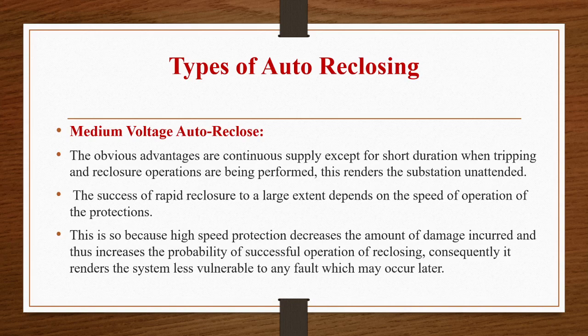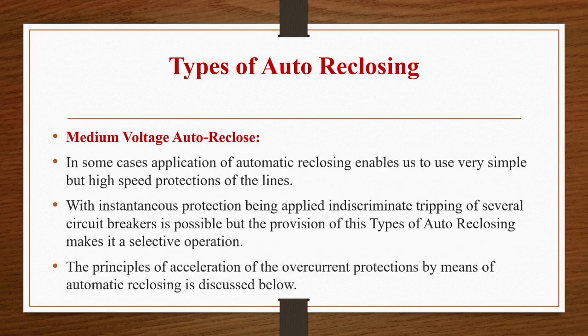This is so because high speed protection decreases the amount of damage incurred and thus increases the probability of successful operation of reclosing, and it will render the system less vulnerable to any fault which may occur later. So the success of rapid reclosure depends on the speed of operation of protections, because high speed protection decreases the damage incurred and increases the probability of successful reclosing.